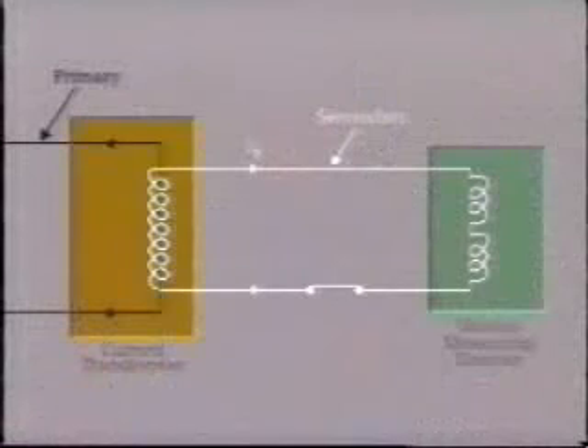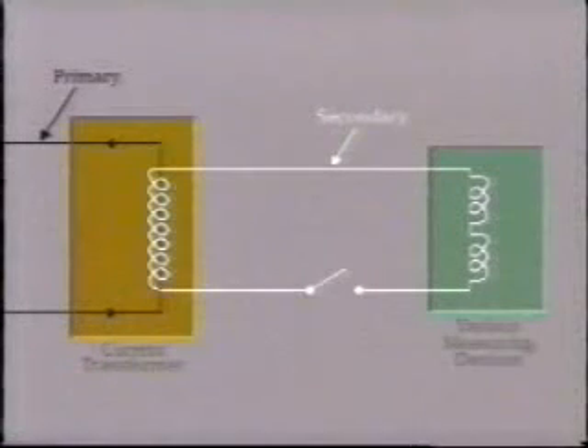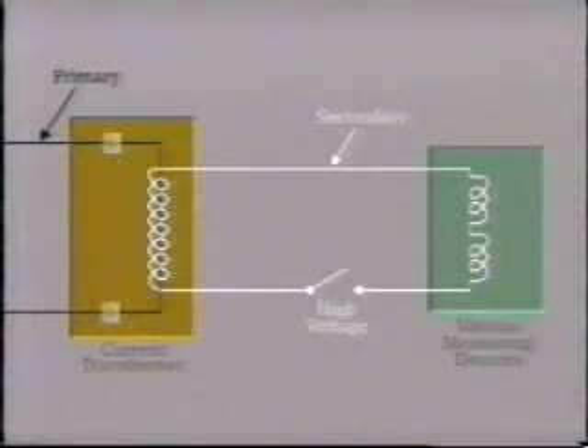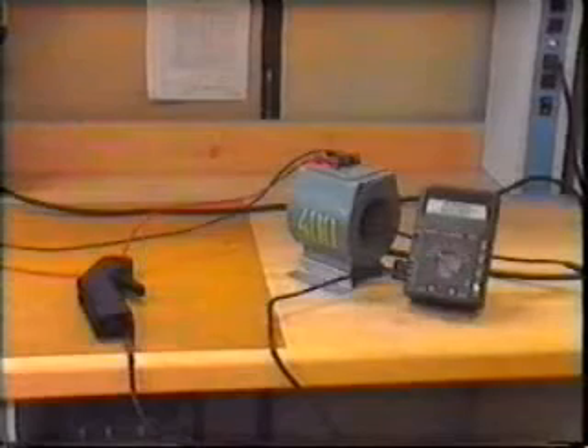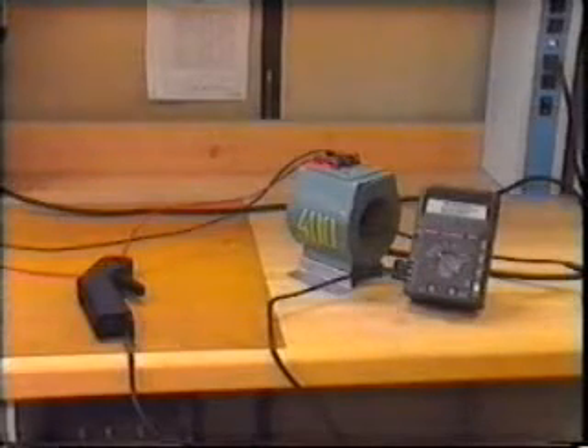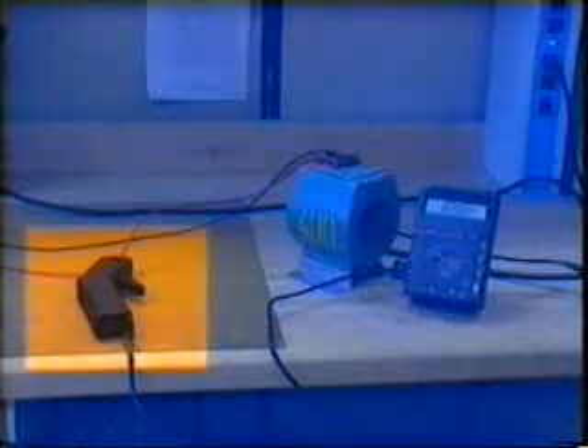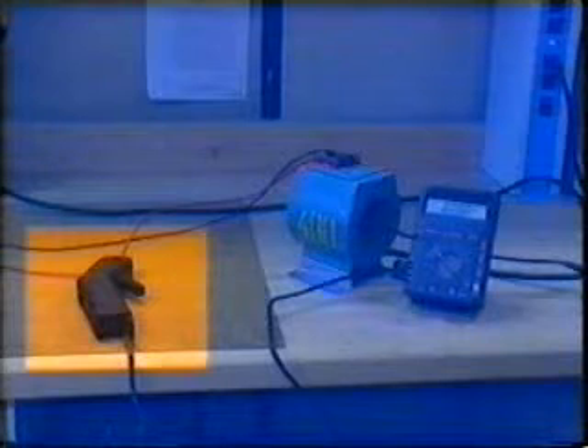In our activities, we are often concerned with measuring current flow in CT secondaries. The multimeter is not suitable for this job because it is fused. As you know, open-circuited CTs are a source of danger. If primary current flows, an extremely high voltage may be induced into the open-circuited secondary. For CTs and other current measurements, clamp-on current probes are most commonly used.